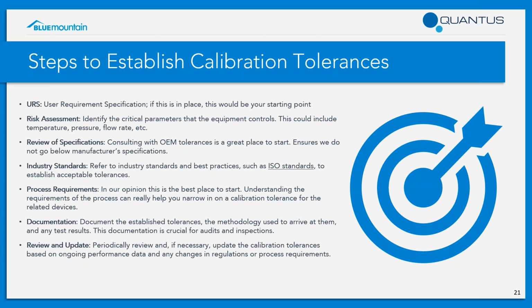A lot of equipment is sold based on the accuracy of the device as a marketing purpose, so they may not always be practical in manufacturers' operations. So again, keep it focused around the process. If you're able to reference an industry standard, that's a really good place to start. Some industry standards that we typically look at are ISO guidelines, something like ISO 8655 for pipettes or ISO 21501 for particle counters. Those documents are really great references because they talk about the exact tests and accuracies that you should be following for your testing. Again, process requirements, in our opinion, are going to be the best place to start.